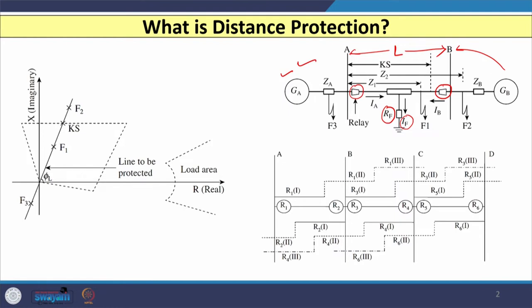If we consider a fault at the middle of this line with fault resistance RF, then two currents are available: one from substation A and another fed from substation B. The fault current IF is the addition of current from substation A and current from substation B. We consider three different fault cases: F1, F2 beyond bus B, and F3 beyond bus A.